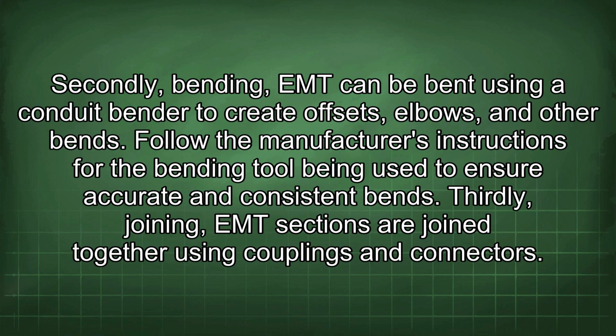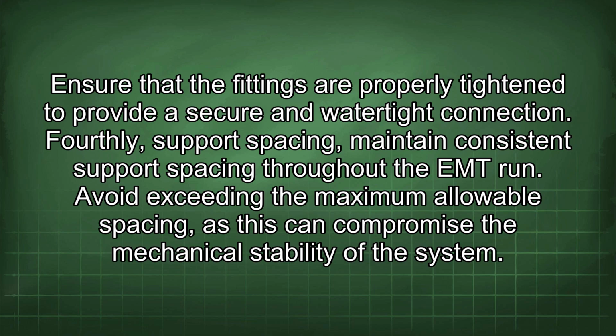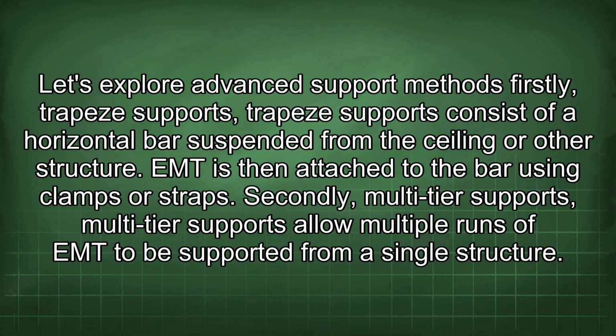Thirdly, joining. EMT sections are joined together using couplings and connectors. Ensure that the fittings are properly tightened to provide a secure and watertight connection. Fourthly, support spacing. Maintain consistent support spacing throughout the EMT run. Avoid exceeding the maximum allowable spacing, as this can compromise the mechanical stability of the system. Let's explore advanced support methods.